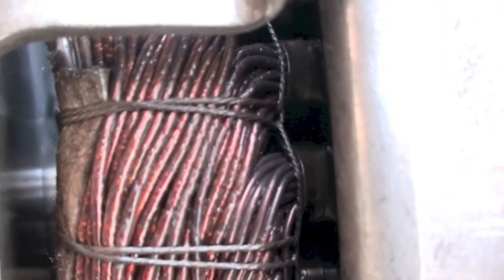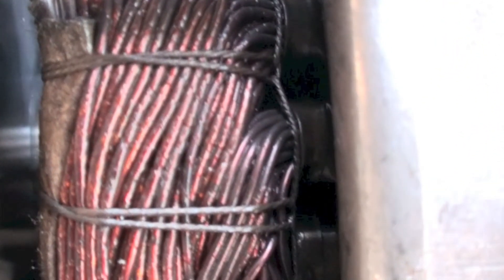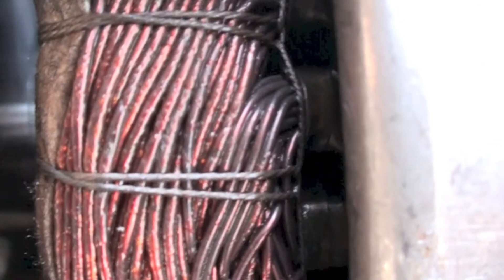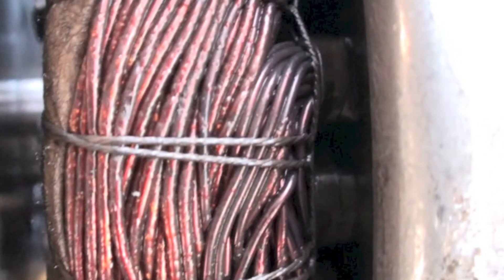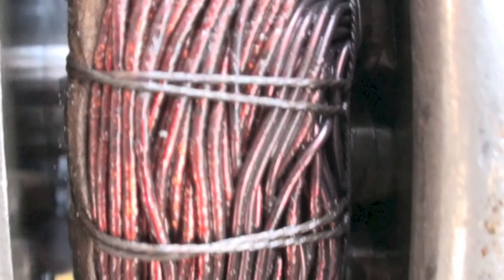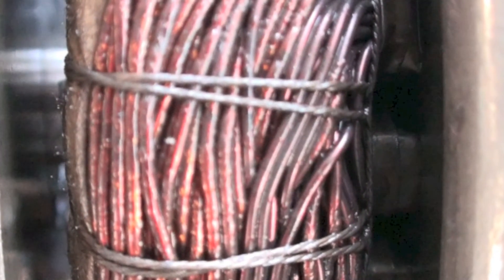Okay, what I want you to see here after a couple of shots of this thing running for a few seconds, you can see what's happened to the windings compared to those windings before where the coating looked pretty good. This looks pretty ugly. That's pretty terrible. That stuff is getting real soft and it's probably just going to burn off here right quick.